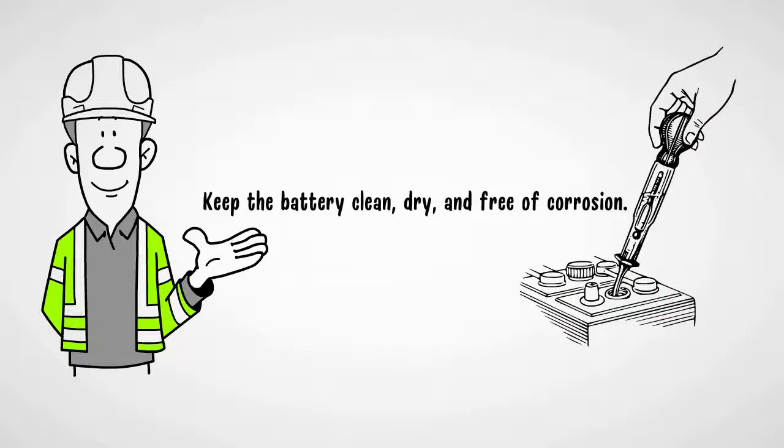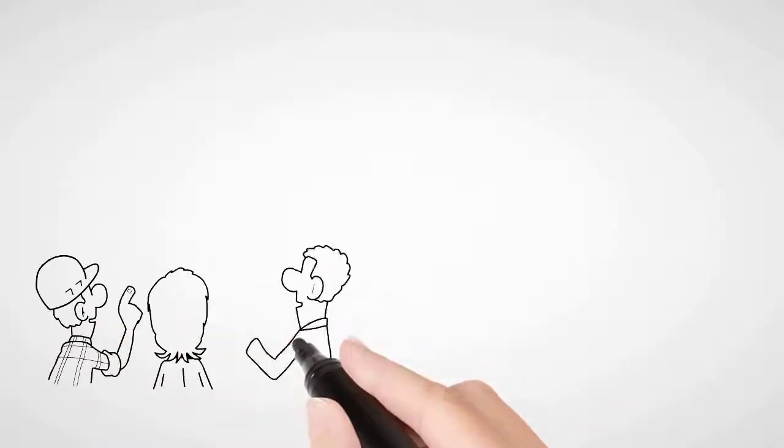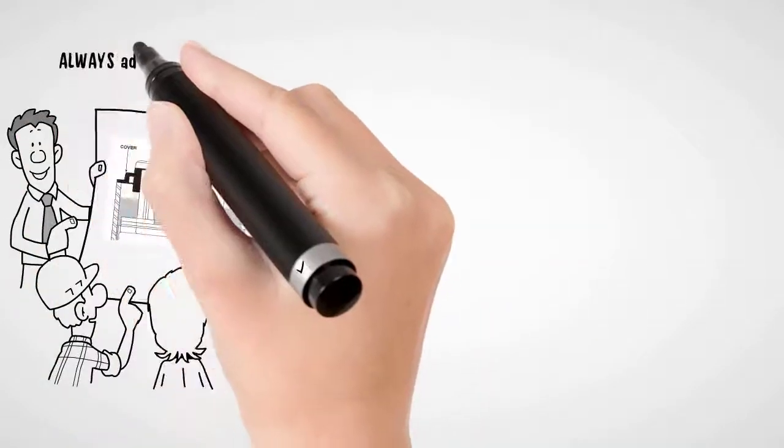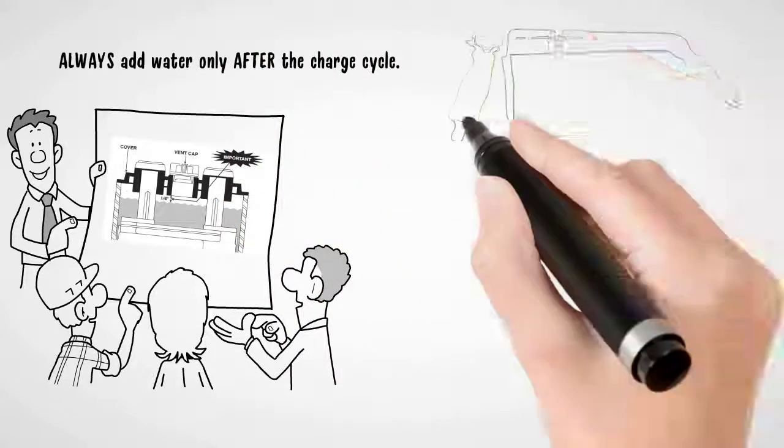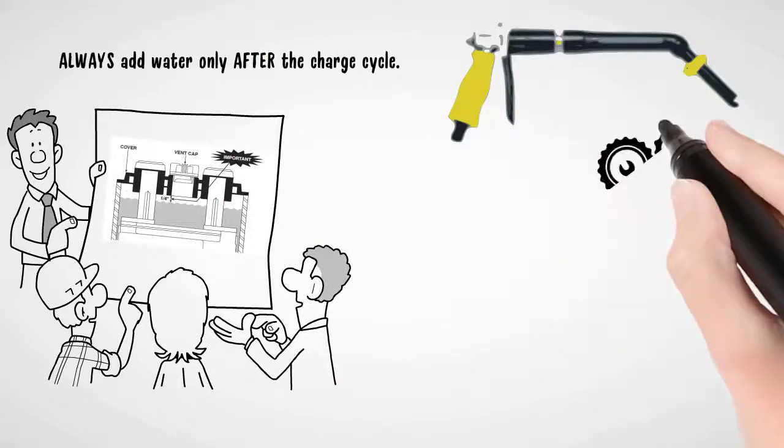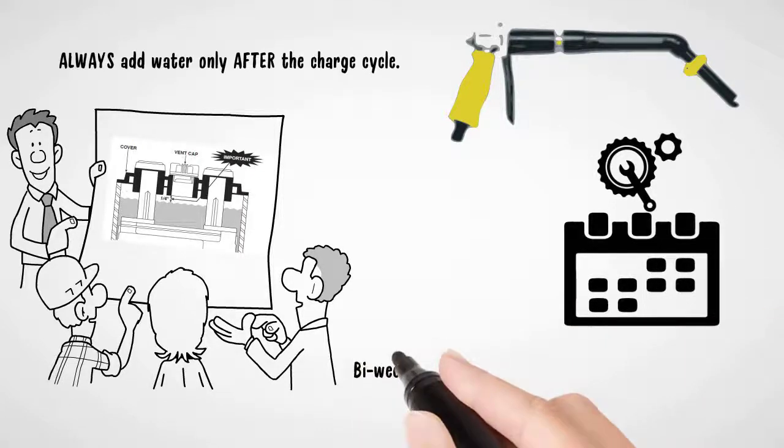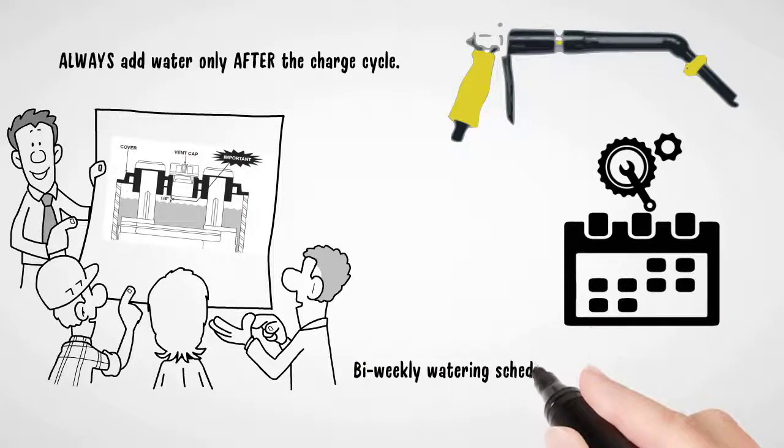Number 2: Maintain the correct water level, which is ¼ to ½ inch below the battery cap opening. Number 3: Always add water only after the charge cycle. Number 4: Set up a weekly or biweekly watering schedule to ensure proper water levels.